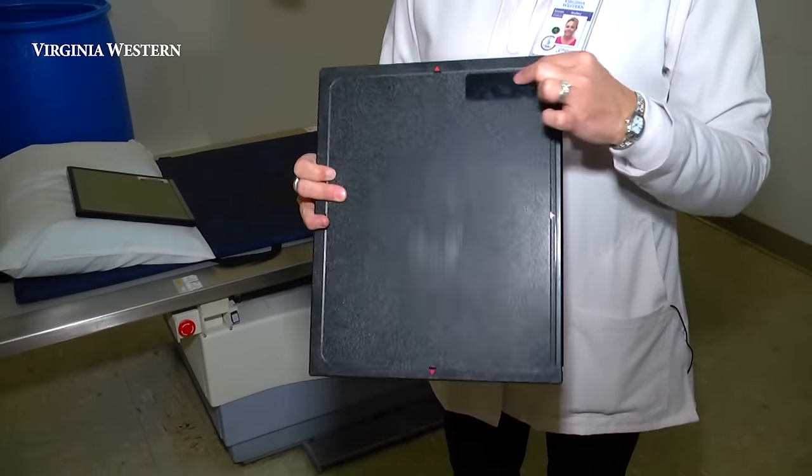Every morning when a technologist comes in, they will turn the processor on, make sure the processor reaches the temperature that is desired. They will take a piece of film out of the film bin, expose it in the sensitometer, and put it through the processor. After processing, there will be a scale that the technologist will measure using the densitometer. They use certain selected numbers on the graph that they use every day. This way, there's continuity in your factors.